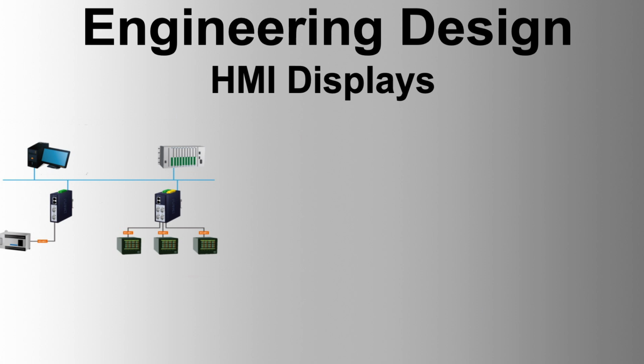Detailed displays, steady state, show schematic views of process equipment within a subunit, including dynamic data and control options for the equipment. Short duration trends for major control loops are included for shift change and subunit analysis. Detailed displays, transients, are reconfigured steady-state process graphics to cater for specific transients and modes of operation, such as startup or process upsets. They assist operators in visualizing and managing the phases and effects of these transients.